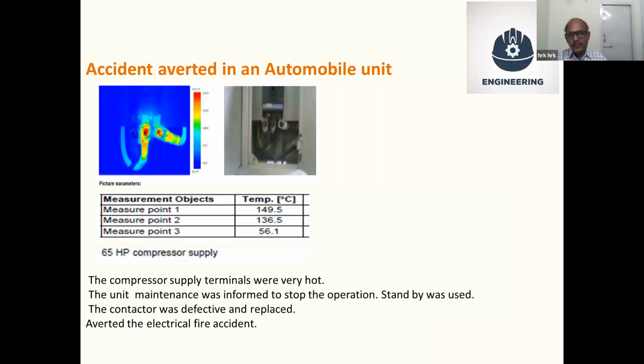Another case was when I was doing thermography of a compressor supply. The temperature was very high, 149, and they immediately stopped the operation and went to the bypass, using another spare compressor for the line. When they checked, the contactors had totally failed, so they changed them immediately. This is a classic example of how we can use thermography to prevent a fire accident, and also equipment failure.